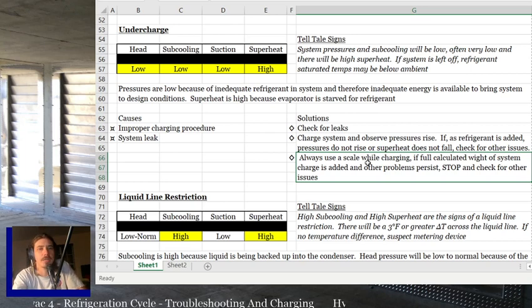So if it's a slightly low charge, everything might look fine. You just have your slightly low head, and a low subcooling. If you're really low on charge, you're still going to have these same values on a TXV. Everything is going to be low, and your superheat's going to be high because the TXV can't open enough to let enough refrigerant through. So it's going to basically behave like a wide open fixed orifice at that point.